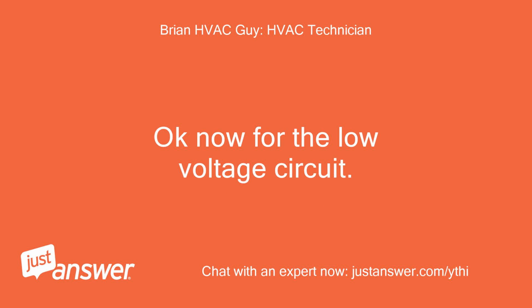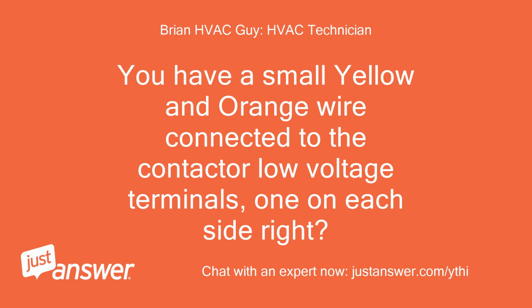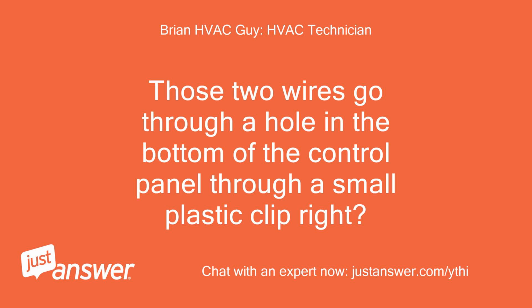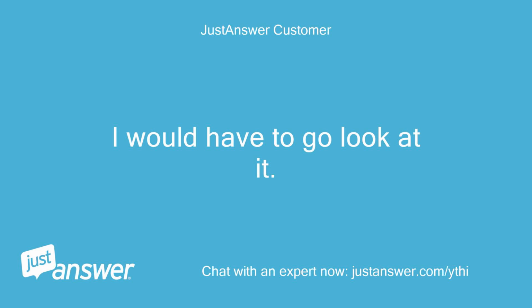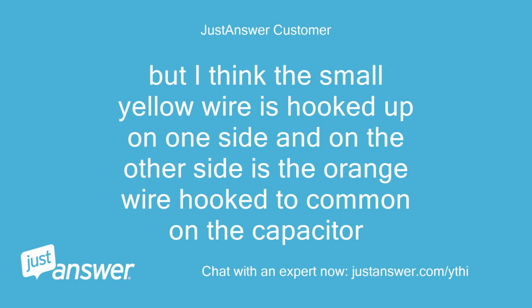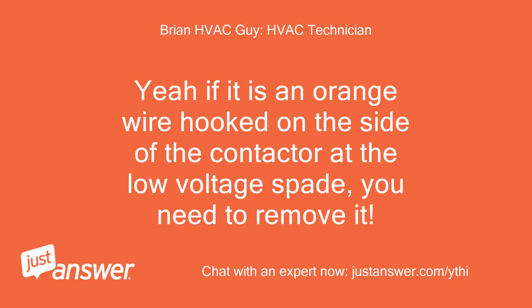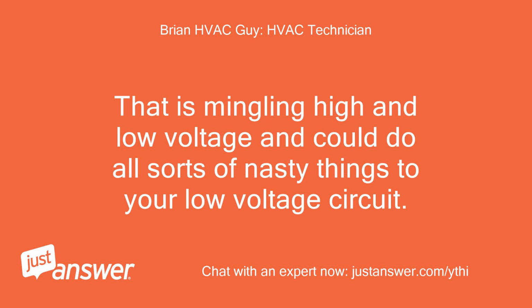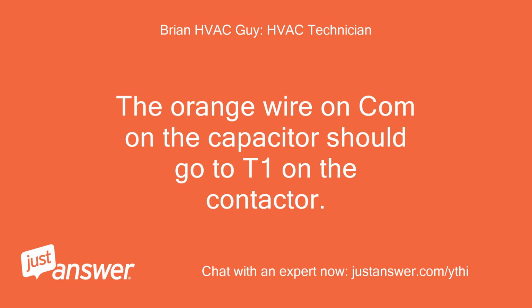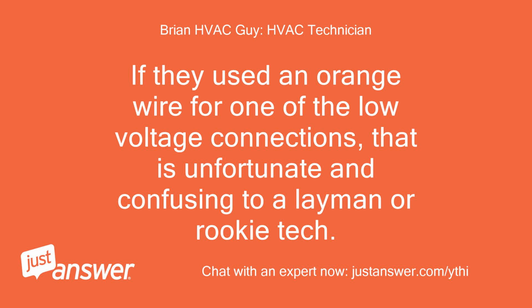Okay, now for the low voltage circuit. You have a small yellow and orange wire connected to the contactor low voltage terminals, 1 on each side, right? Those 2 wires go through a hole in the bottom of the control panel through a small plastic clip, right? I think so. I would have to go look at it. But I think the small yellow wire is hooked up on one side and on the other side is the orange wire hooked to common on the capacitor. Yeah, if it is an orange wire hooked on the side of the contactor at the low voltage spade, you need to remove it. That is mingling high and low voltage and could do all sorts of nasty things to your low voltage circuit. The orange wire on COM on the capacitor should go to T1 on the contactor. If they used an orange wire for one of the low voltage connections, that is unfortunate and confusing to a layman or rookie tech.